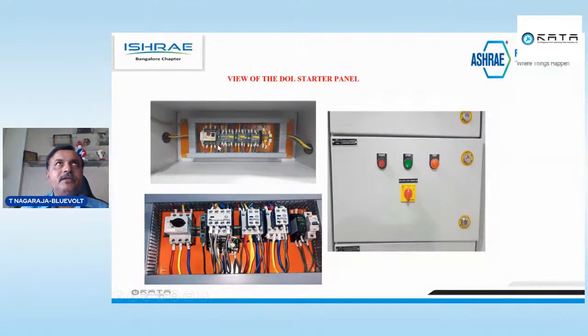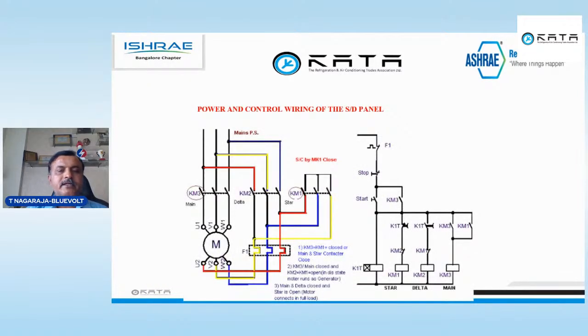The timing should be 4 to 6 seconds maximum, based on your fan application. Sometimes it will be less, because with forward curve fans the inrush current will be very high. You may ask why it runs at 50% in star delta. Because your voltage will be 50%. When the motor needs 415 volts, you are giving less at starting.